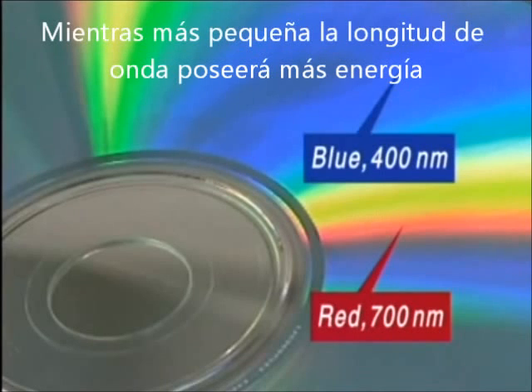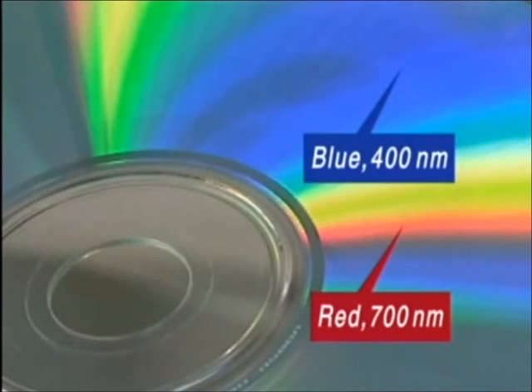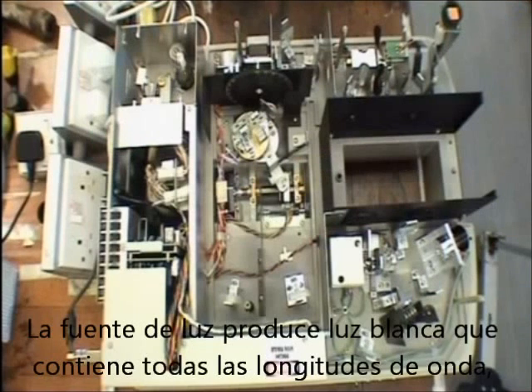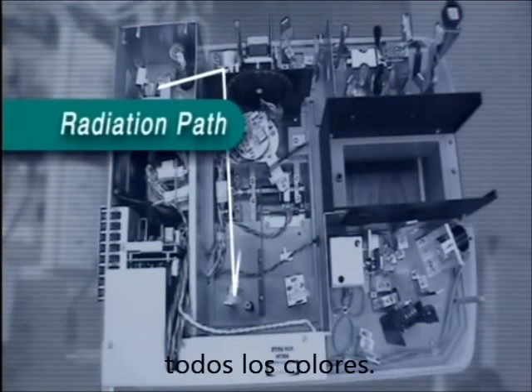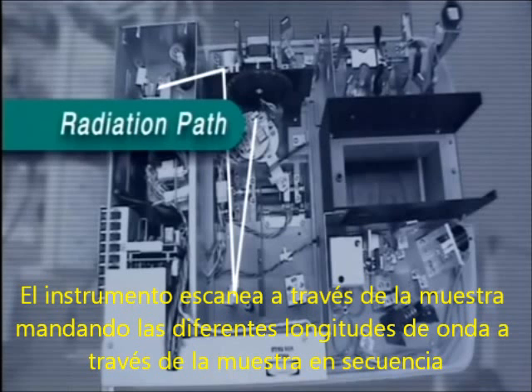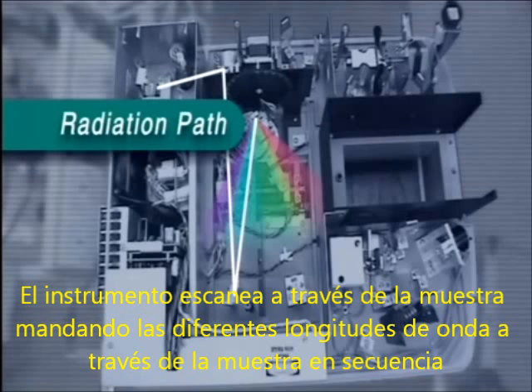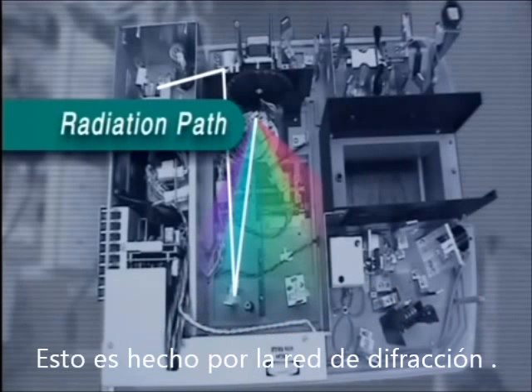Shorter wavelength light has higher energy. The source produces white light that includes all wavelengths, all colours. The instrument scans through the spectrum, sending different wavelengths of light through the sample in sequence. This is done by the grating, which rotates.